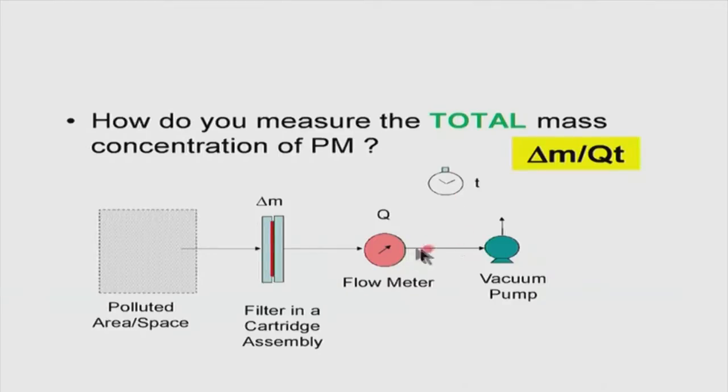One of the issues that also comes up is the weighing machine that you have. Last time we talked about doing this flow of 10 liters per minute for 10 minutes, which means the total in the denominator would be 100 liters. Sometimes if the concentration is high, you'll get sufficient mass to be able to do this calculation. But if the particulate matter is small and the contribution to mass is less, then that 100 liters may not be adequate for you to get a detectable amount of mass. So you may have to run either at a high Q value or for a longer time.